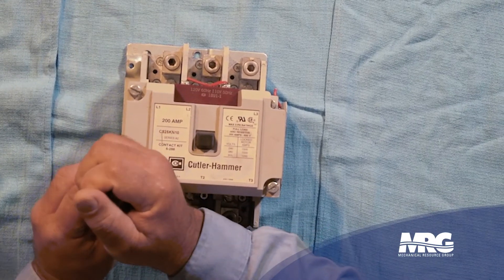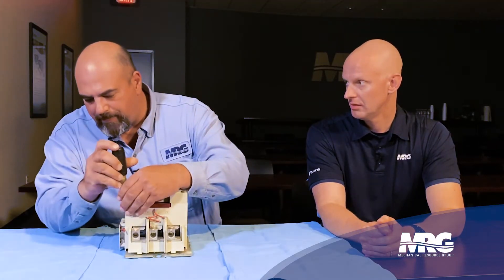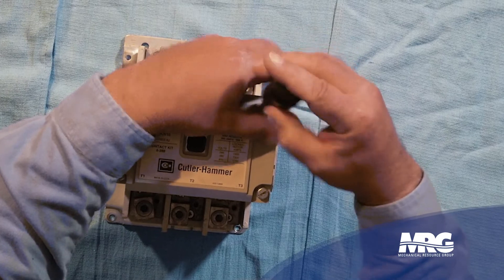These contactors are quite common in industrial and commercial chiller applications, also fans and other instruments. There is a proper sequence to disassemble this type of contactor and maintain it. This one is from an old Trane CBH-E chiller that we converted to a VFD. I kept these as spares to actually demonstrate how we can pull these things apart. And this is a 200 amp contactor.